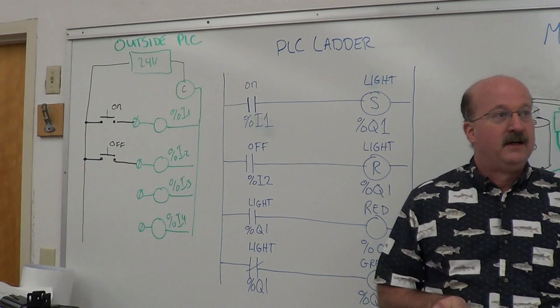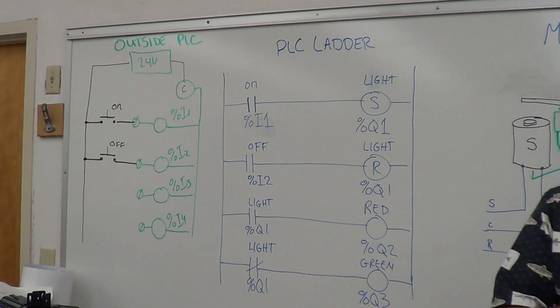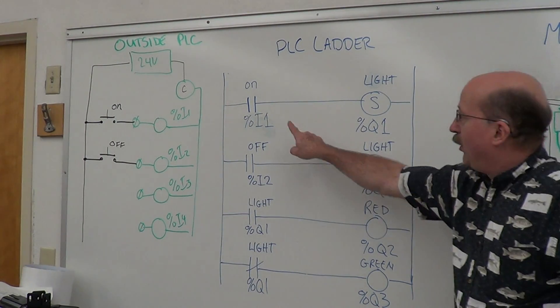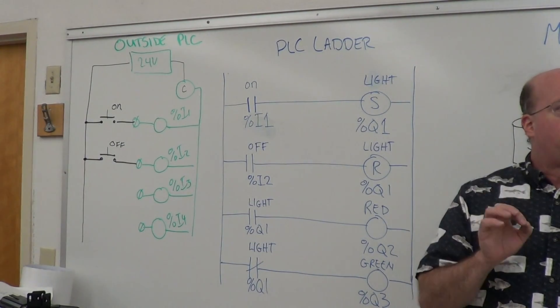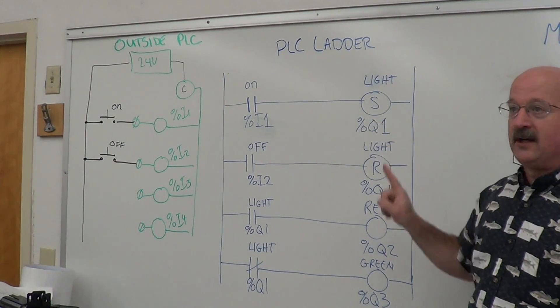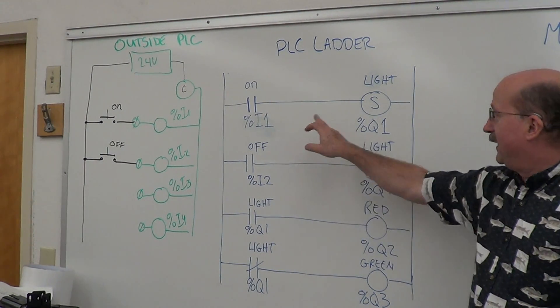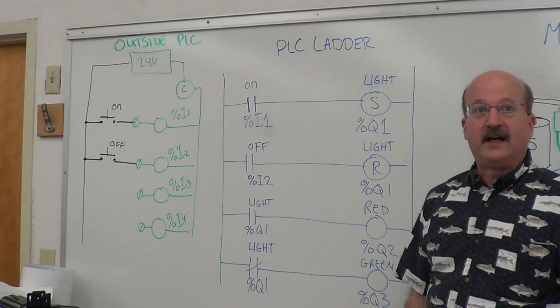Now unlike the mechanical relay, where you have to have it of sufficient duration to cause the mechanical switch, you only need this to be closed or true for one scan and it will cause a switch. One scan. If that's true for one scan, your switch will set or reset.